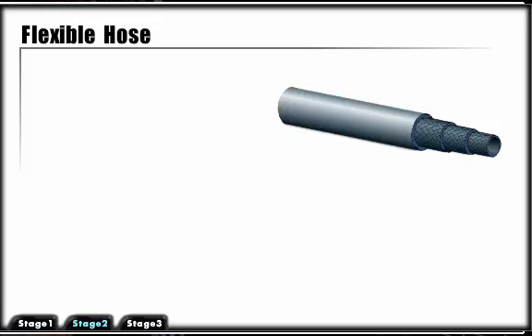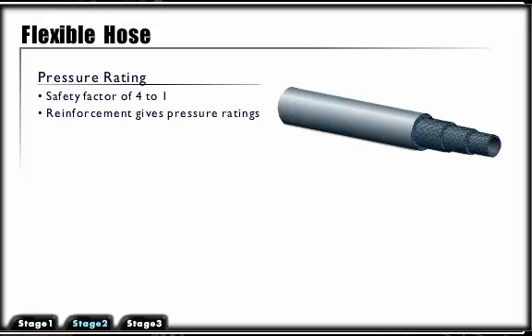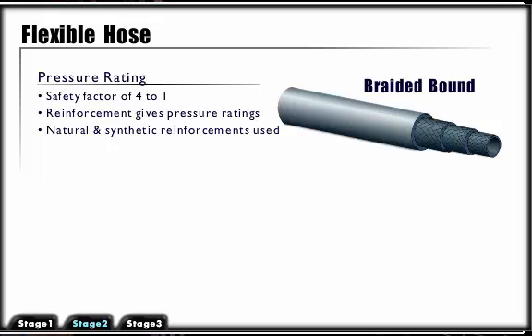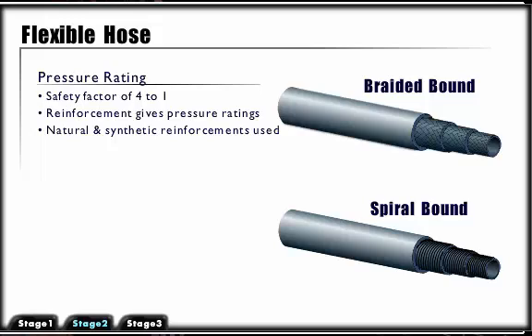Hoses are usually pressure rated with a safety factor of 4 to 1. Different types and amounts of reinforcement give the hose specific pressure ratings. The reinforcement may be in natural or synthetic fiber or metal wire, and may be braided or spiral bound.